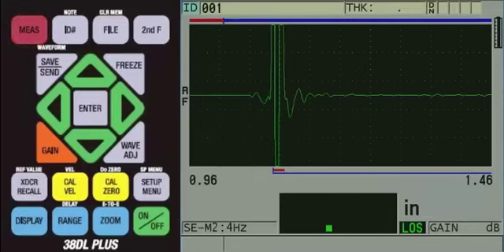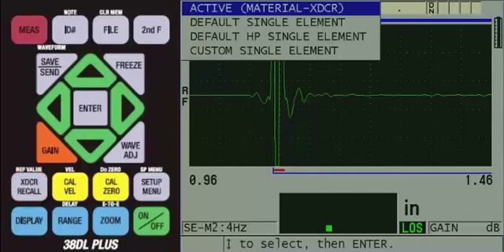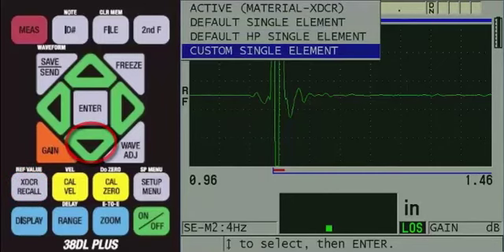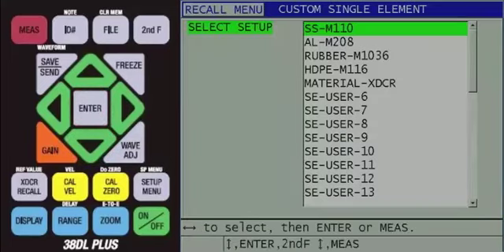To recall this saved setup, press the XDCR recall key to highlight Custom Single Element, and then press the Enter key. Use the arrow key to highlight the name of the custom transducer setup. Once highlighted, press the red Measure key to recall the custom transducer setup.